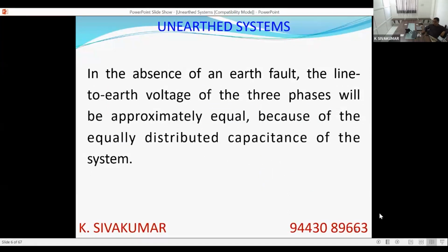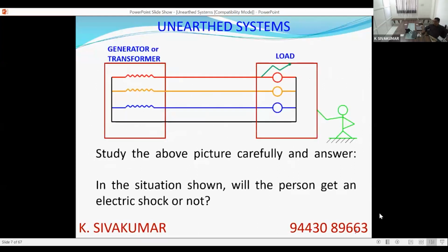Suppose there is no earth fault in the system, the three phase line to earth voltages will be approximately equal, because we presume that the capacitance is equally distributed. To simplify things, we presume that this is equally distributed. Now, do not think of very complicated capacitive coupling, all those things. Just look at this picture. If you say that this system is unearthed, the R phase is touching the metal enclosure of the load. A person is in direct contact with the metal enclosure. Worst condition: wet foot, barefoot, wet floor, all those conditions you assume.